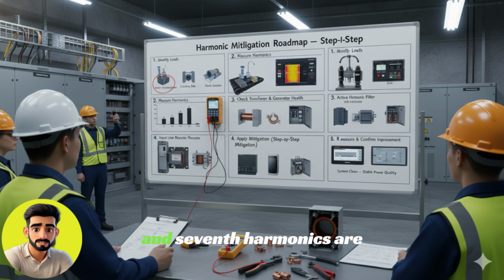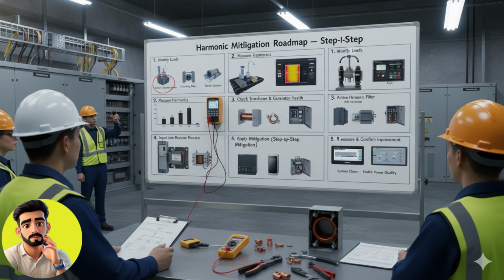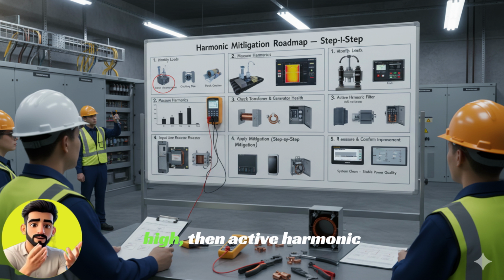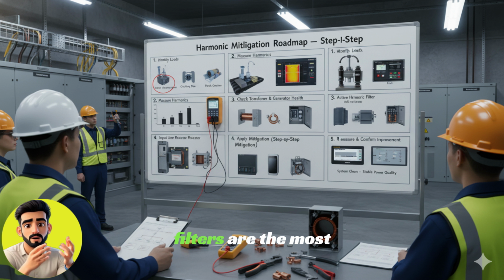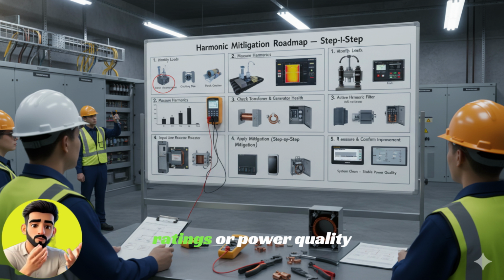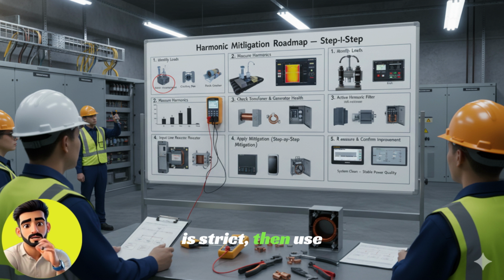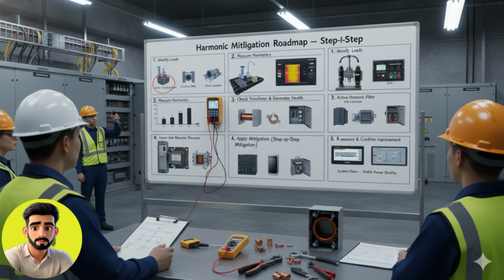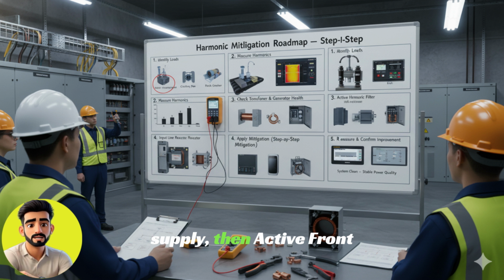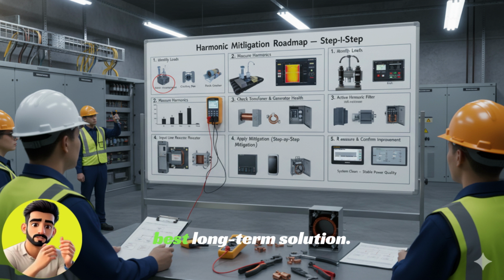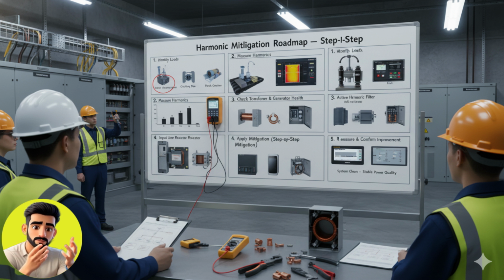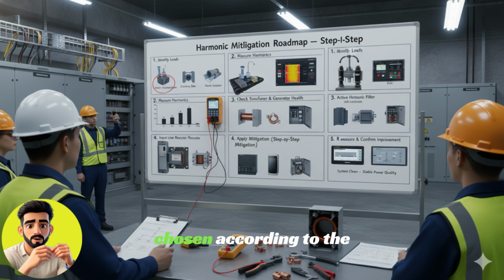If only the fifth and seventh harmonics are high in the plant, use passive harmonic filters. If mixed harmonics are high, then active harmonic filters are the most powerful solution. If drives have large ratings or power quality is strict, then use multi-pulse drives. If the plant is critical or has generator-based supply, then active front-end drives are the best long-term solution. The solution is always chosen according to the size of the problem.